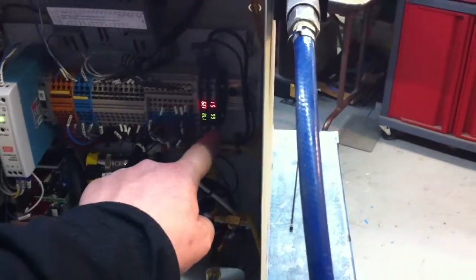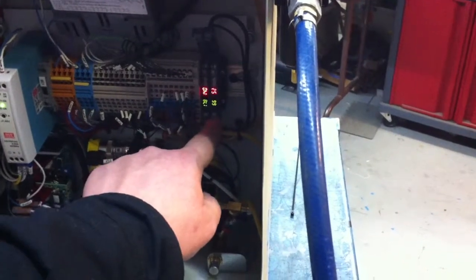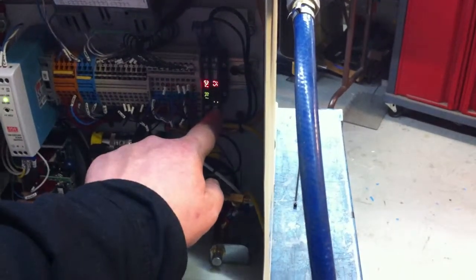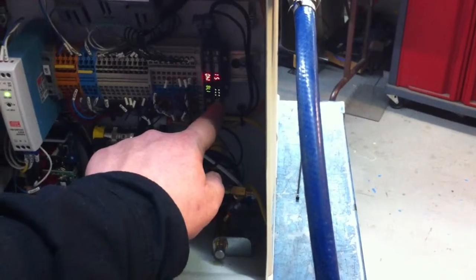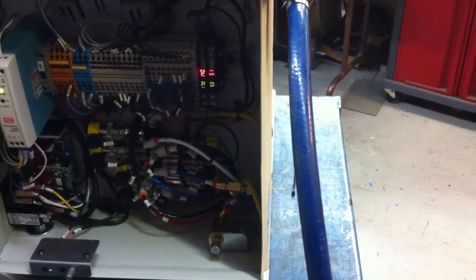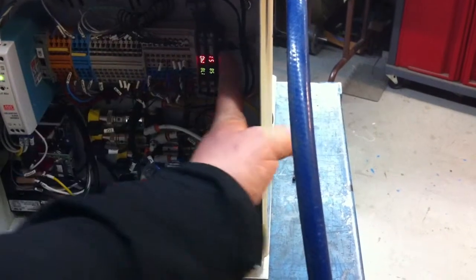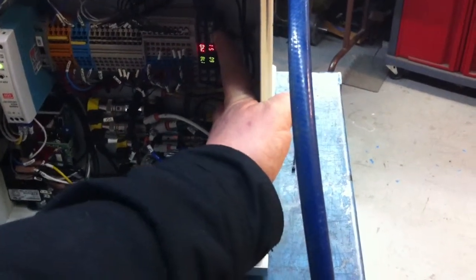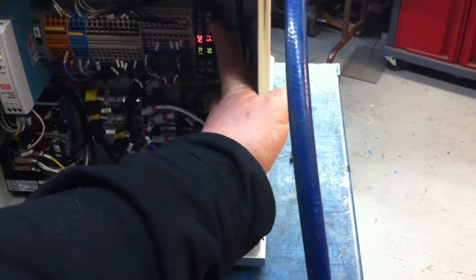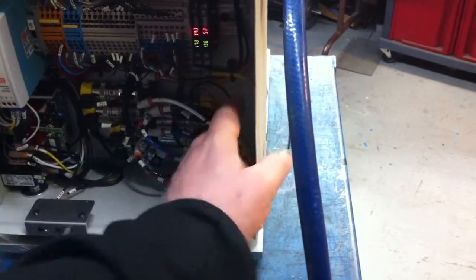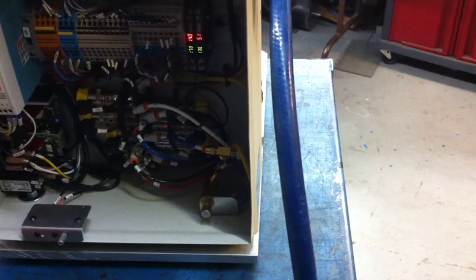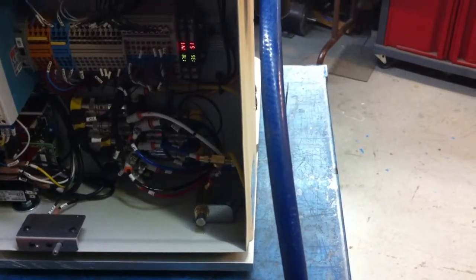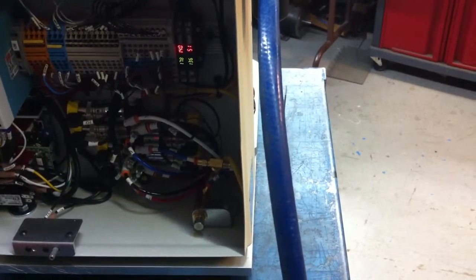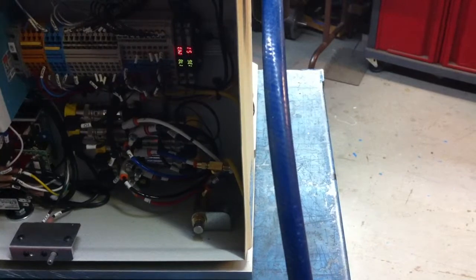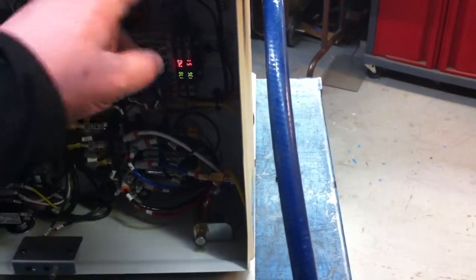This bottom button right here, right above that, there's a little LED. You hold down the button and you'll have 3 bars that come on, and then they'll flash. Now the fiber optic's set. I sometimes will increase my green number to about 50 to 100 over the red number. That just gives me a little bit finer range, and it keeps it from being so touchy. Keeps that dust and debris from setting it off. But it's really easy to set the fiber optics.